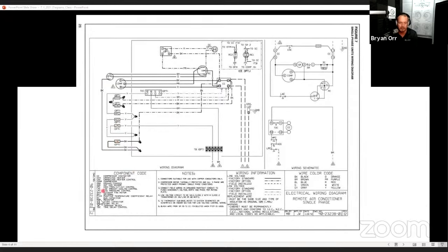Another really nice thing to do is to do your own as-built. So take a piece of equipment and draw your own ladder schematic. And you're going to want it to be a basic unit. I would not suggest trying to draw point to points because that's more about art than it is about drawing a proper schematic. But actually start with your L1 and L2 and draw all your circuits going in between. That's a really good exercise to get better at schematics.